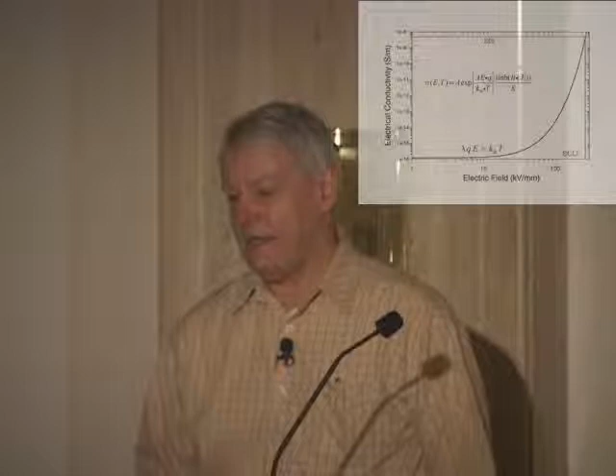Now, we can get some insight into these phenomena experimentally using the guarded needle technique, which was developed by Zeller and Pfluger at ABB. This is an example of a needle. This has a 5-micron tip radius, about 30 microns of exposed needle, a couple of microns of epoxy, and then there's chromium evaporated on top of the epoxy to form a guard, so that this thing is guarded to within 30 microns of the tip. This gives you a capacitance of a few femtofarads to the high voltage electrode and allows you to measure the image charge on the needle tip, which results from carrier mobility within the dielectric.